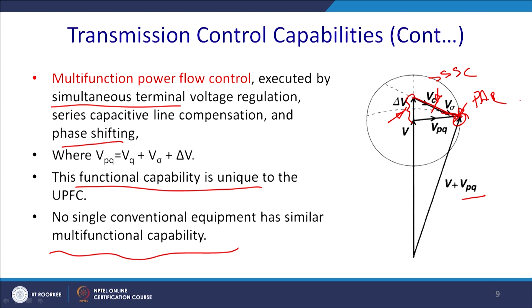Because we see that it is a quite versatile device, how does this power flow, and how can its power flow be controlled? For the real and reactive power transmission versus transmission angle characteristics, we have to go back to our two machine model. The characteristics of the simple two machine system for the uncompensated system were already discussed in series and shunt compensation. That will be the takeaway, because it depends on which mode of operation you select. If you select this mode, which is basically the tap changing transformer, that equation will come into the picture. If you take this mode of operation, then it is the SSSC's operation, and if you say V sigma operation, that will be the PAR operation, and accordingly the rating will change.